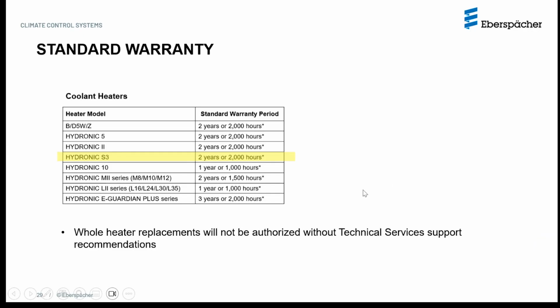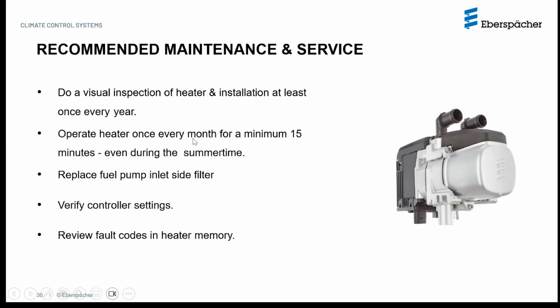Okay. So now, having said that, what about service and maintenance? Visual inspection of the heater at least once every year. So as you know, the heater is under the floor. It's exposed to the elements. You could have things flying off the road, hitting the parts like exhaust, intake tubing, etc., breaking it. So inspecting that heater once a year, preferably before the heating season begins, is always recommended. Another important recommendation is to operate the heater once every month, minimum 15 minutes.